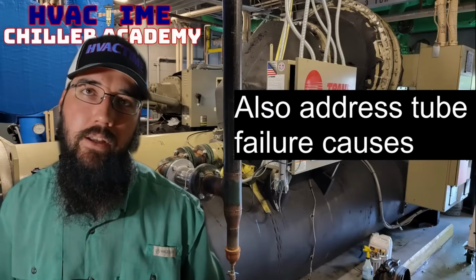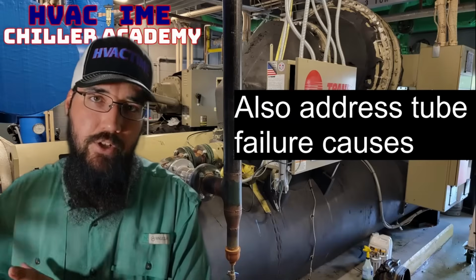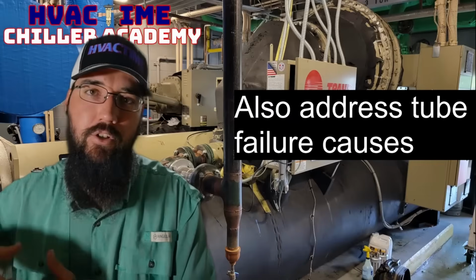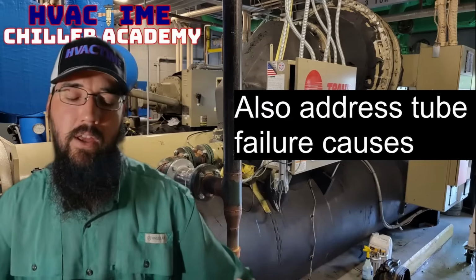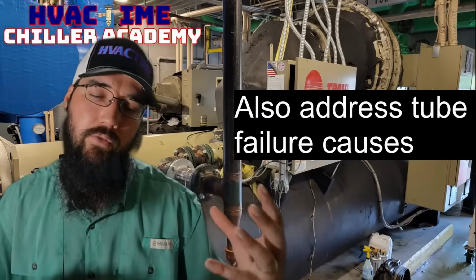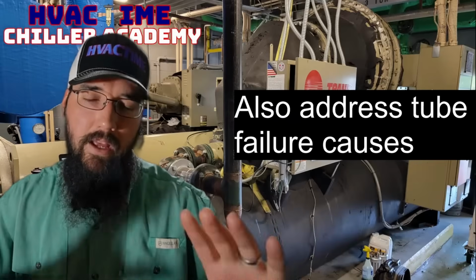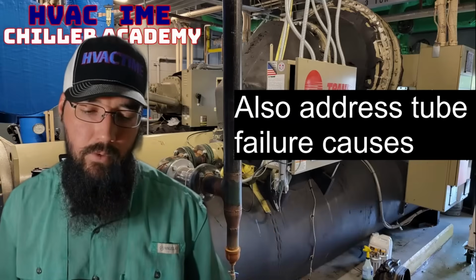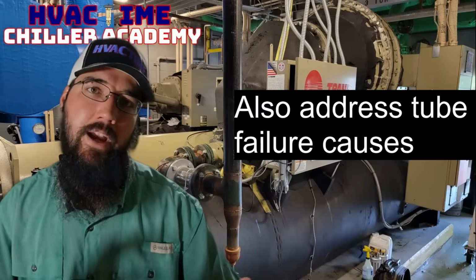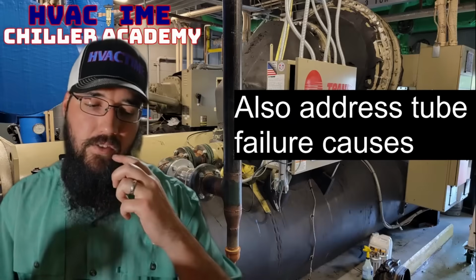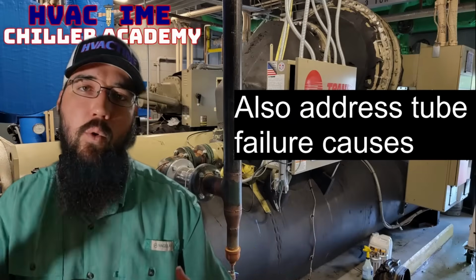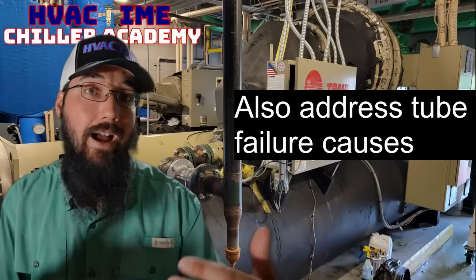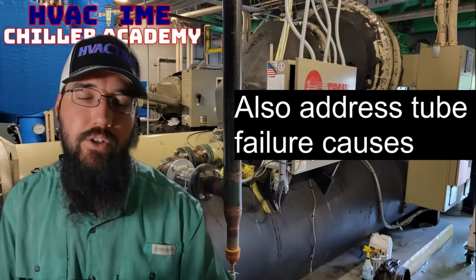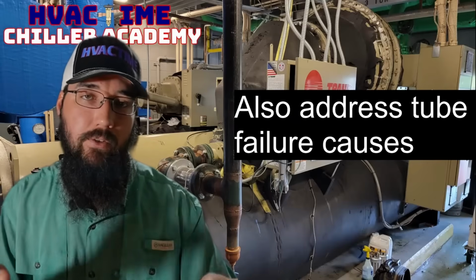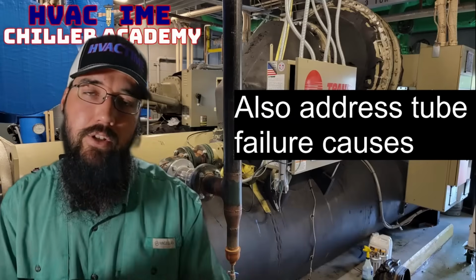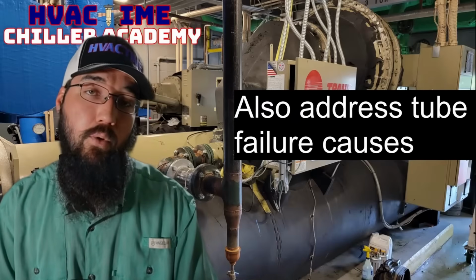Now, another one is the actual end plate itself. Expansion and contraction from the water cycle of heating up and the chiller shutting off, shutting down, different seasonal shifts. So anytime that metal is getting hot and cold, you've got steel end plates for the tube sheets, and then you've got copper tubes most of the time in what we're working on. Well, those metals expand and contract at different rates. Enough of that over time, or just general vibration, where high excessive flow can cause additional vibration, can contribute to those tube sheets where the tubes themselves are swedged into the end plate. Those can become leak points as well.